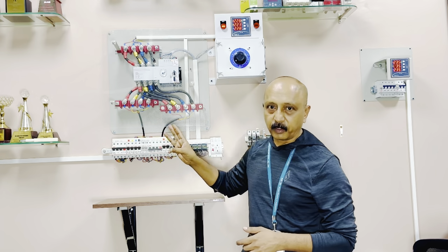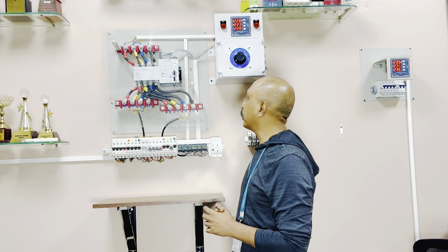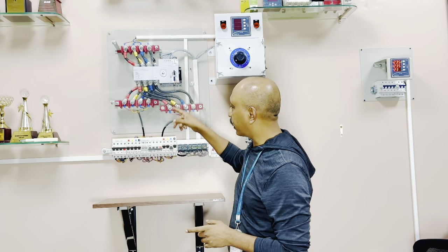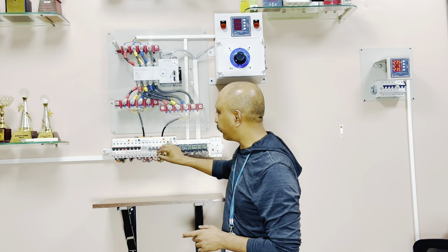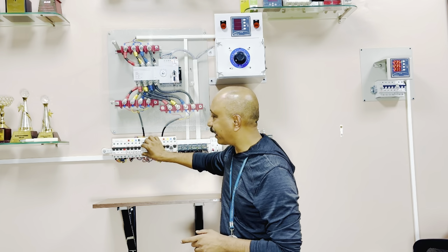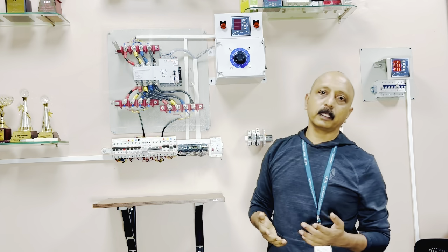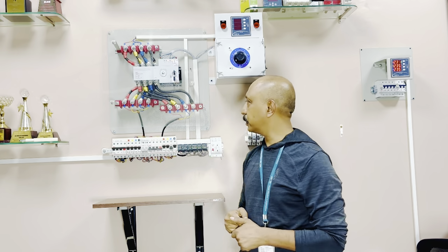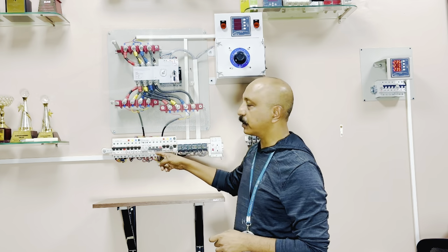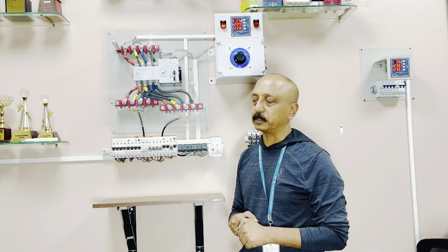All 3 phases are available, but the phases have flipped. So it recognizes that and goes into an off mode. This is another feature, which is an optional feature. Only when you want it, you will have to predefine it to us. So before the material gets dispatched, we will enable that feature and dispatch it. When the phase sequence is back to normal, the switch moves into source 2 position.